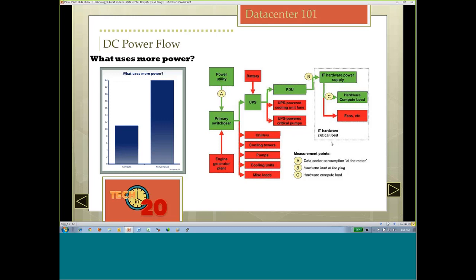A power panel may have 48 breakers, so now I can send those breakers down to different power panels or power strips on the rack, and then the rack will have a set of A and B side power there that you can plug your computing equipment into. So it kind of gives you an idea of how the data center sees power from the street into the actual compute environment itself.